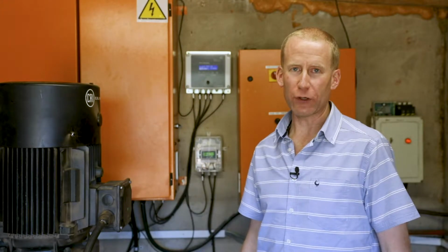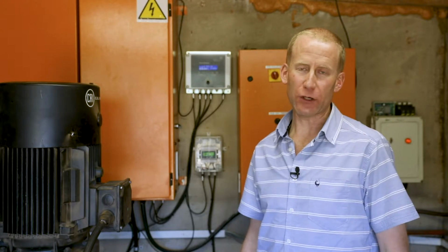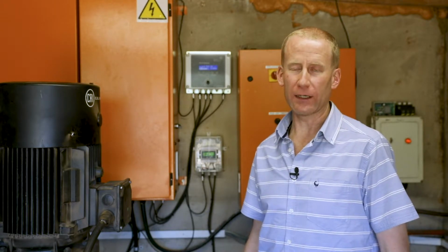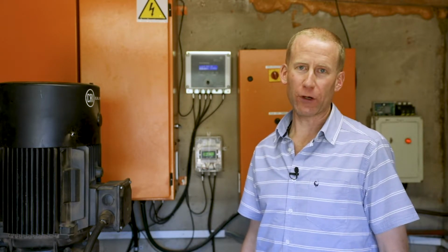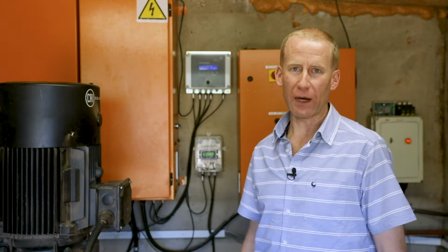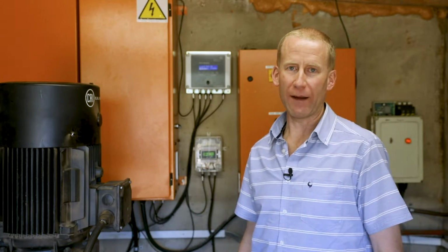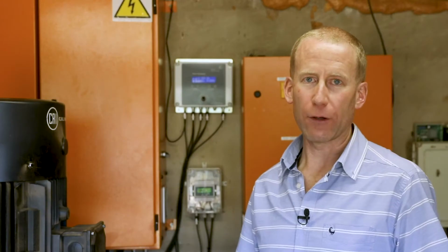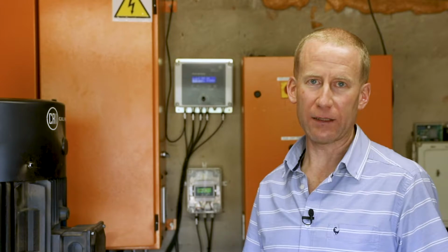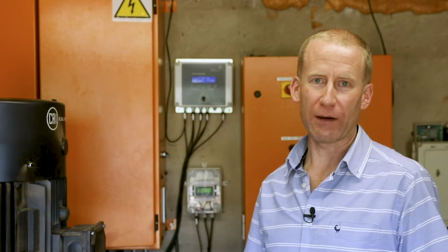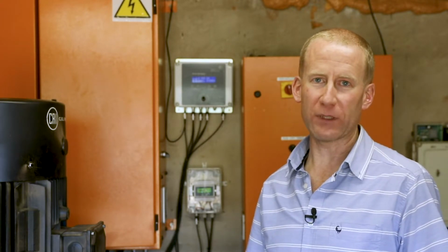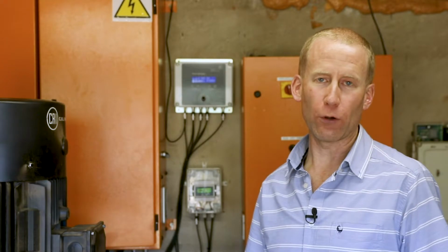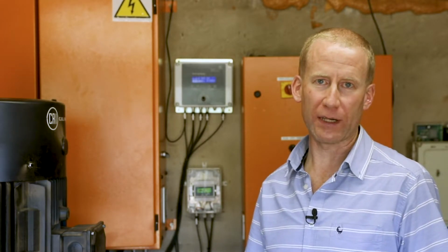The pump outlet pressure, flow rate and electrical power is also monitored. The inlet pressure, outlet pressure and flow rate is used to calculate the hydraulic power delivered by the pump. The ratio of the hydraulic power to the electrical power absorbed by the motor is the combined pump and motor efficiency. A good pump efficiency is around 80%, while a good motor efficiency is around 92%. When you combine 80% efficiency with 92% efficiency, you get a good overall pumping efficiency of around 74%.